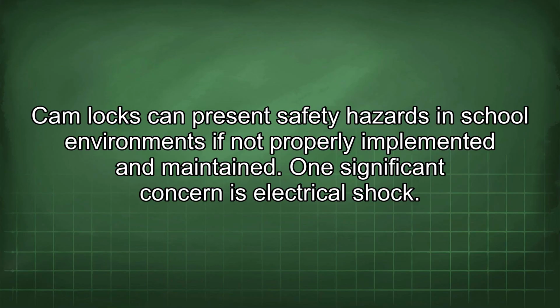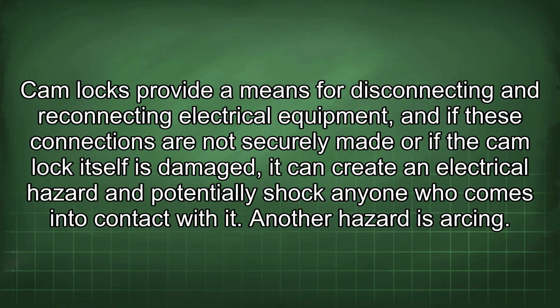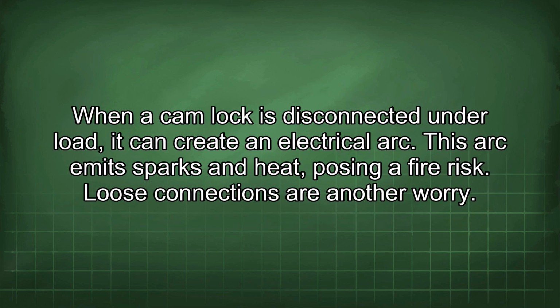Cam locks can present safety hazards in school environments if not properly implemented and maintained. One significant concern is electrical shock. Cam locks provide a means for disconnecting and reconnecting electrical equipment, and if these connections are not securely made or if the cam lock itself is damaged, it can create an electrical hazard and potentially shock anyone who comes into contact with it. Another hazard is arcing. When a cam lock is disconnected under load, it can create an electrical arc. This arc emits sparks and heat, posing a fire risk.